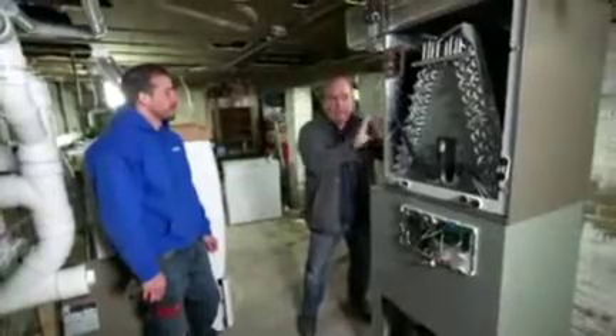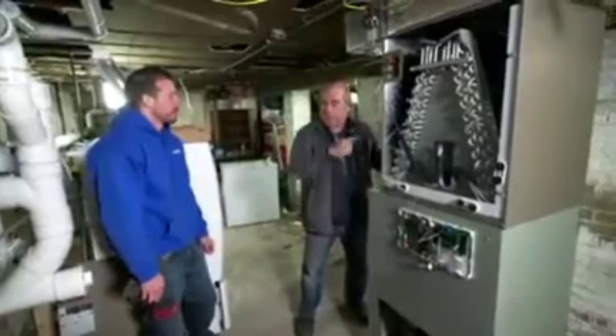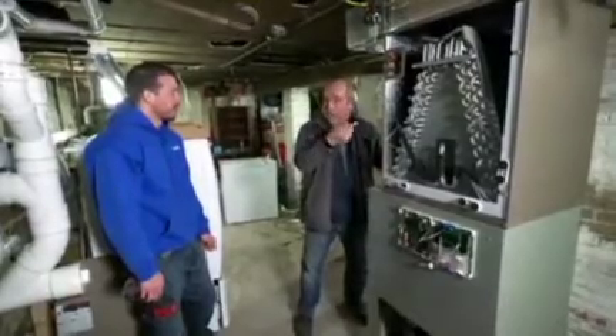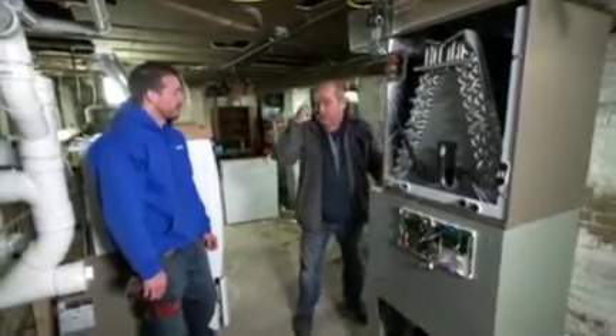What makes it different is that before this came around, if you wanted to add a heat pump coil to an existing furnace, you'd have to go to the manufacturer and get their matched unit, so the fan would just run on full as a tandem. With this, it doesn't really care what's below it. It's smart enough to do just the right amount of output based on what's inside its brain.